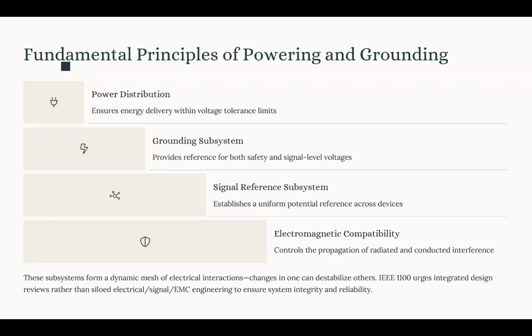There is also a recommendation about topology selection. Single point grounding is used for low frequency analog or audio systems to avoid circulating current. We also have multi-point grounding, or hybrid, which is for high-speed digital systems, so we can reduce the impedance to the high-frequency transients.